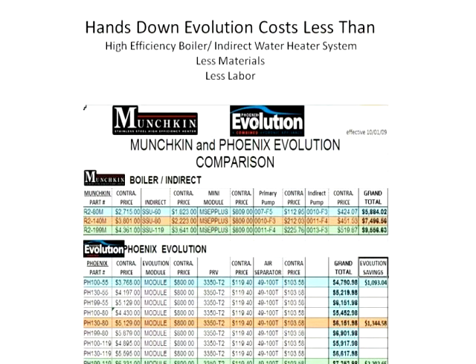These are just quick snapshots, but every way we put it, when you put a quality condensing low mass device with an indirect water heater, and the primary secondary piping that needs to go between the two and the circulator going to the indirect water heater, you're going to have significant savings. We've also studied and gotten data from a variety of contractors, and between the actual component parts and the savings in installation, between this and an indirect and a boiler, we're talking about a couple of thousand dollars in cost. I know it's hard for us all to conceive of that, and you think, oh gee, a Phoenix or a Phoenix Evolution is expensive, and the question is, compared to what?